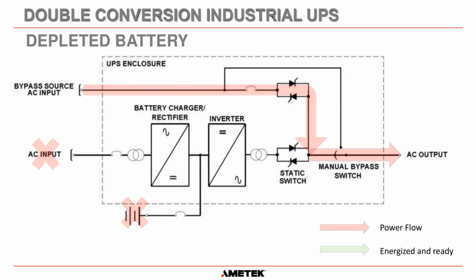And once again, notice that in a full industrial UPS, we do not use a contactor on this branch here to bypass the static switch once we've switched over. This static switch is rated to carry the full system load the whole of the time. So there isn't another point of failure when we transfer to a contactor, because contactors are obviously mechanical devices and they can fail. Static switches are semiconductor based and very, very, very rarely fail, and they switch instantaneously.